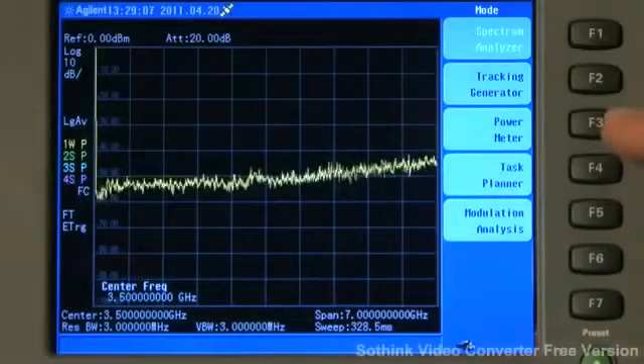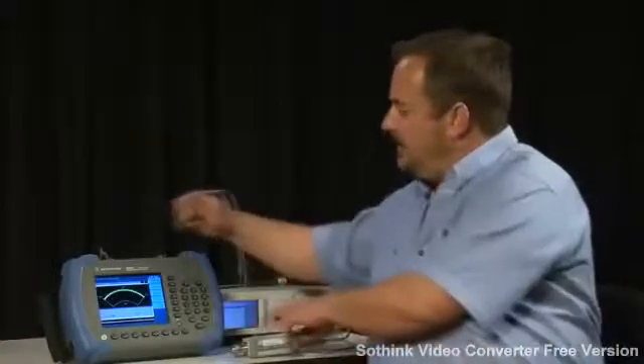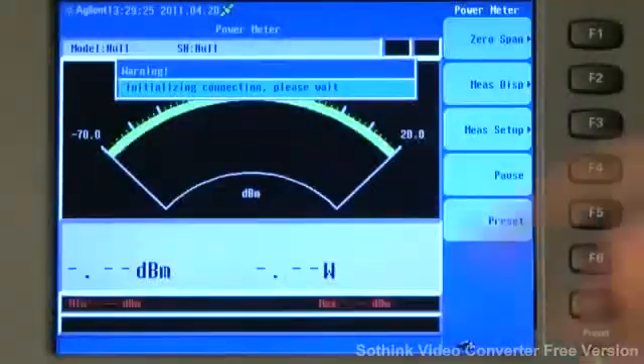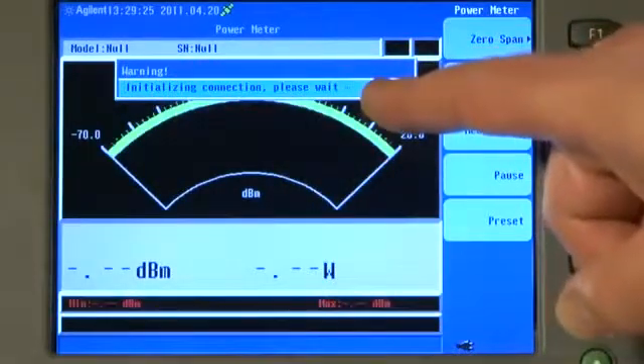We just press the Mode key and select Power Meter. I'll plug the USB lead into the USB port on the analyzer. You'll see the power sensor has been recognized and is initializing.